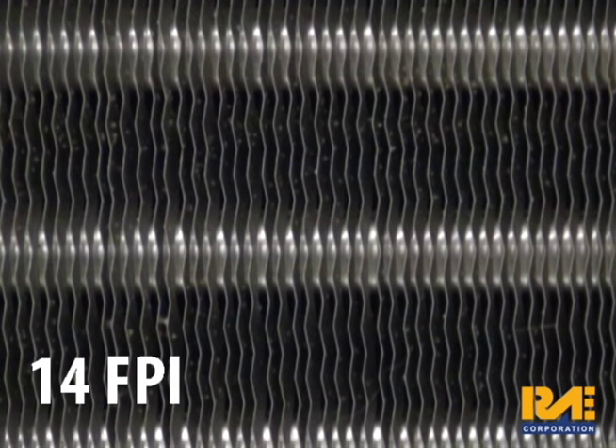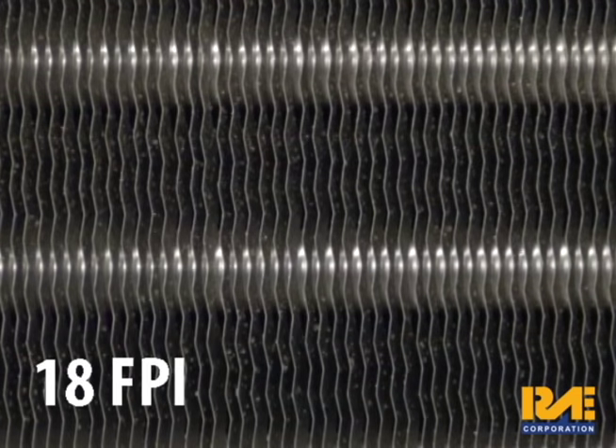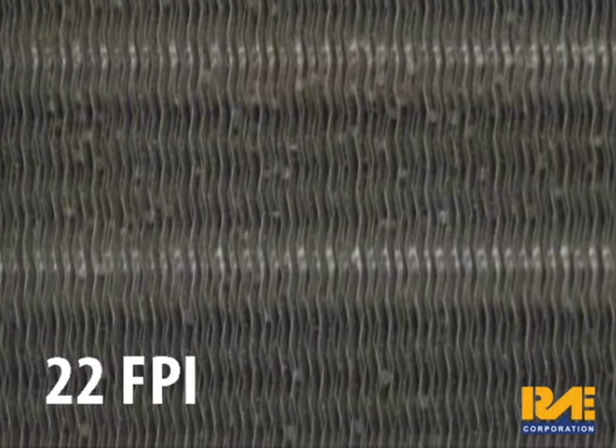It is our opinion that tighter group fin spacing should be avoided if long-term efficiency is a consideration. We manufacturers have been very innovative in our approach to comply with regulatory requirements. However, there can be unintended results. We hope this video has been helpful.